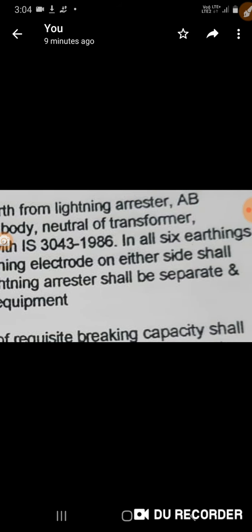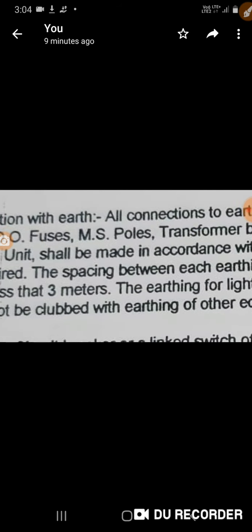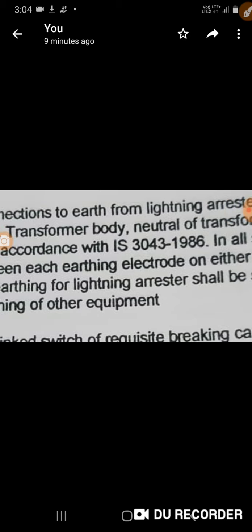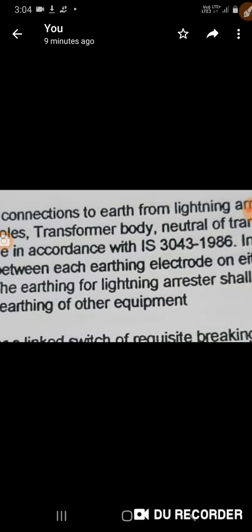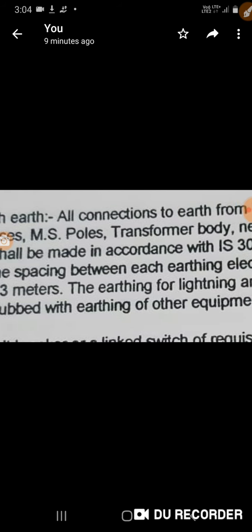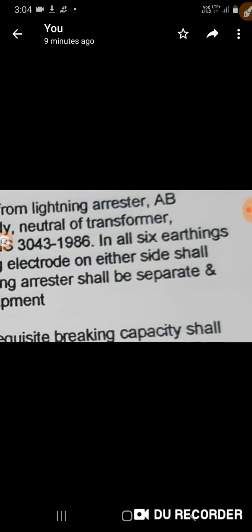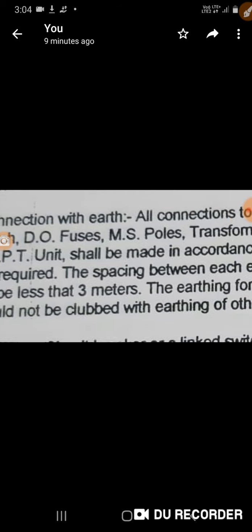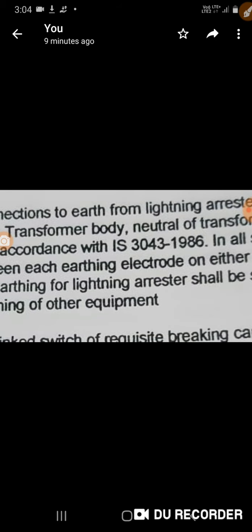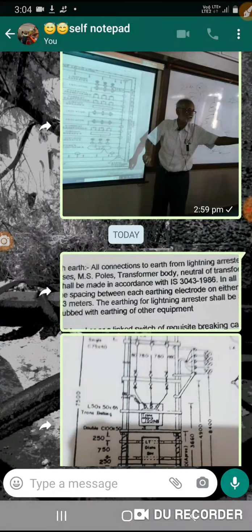In all, 6 earthings are required. 6 earthings means 6 electrodes. The spacing between each earthing electrode on either side shall not be less than 3 meters. The earthing for lightning arrestor shall be separate and should not be clubbed with earthing of other equipment. In fact, we have two separate electrodes.